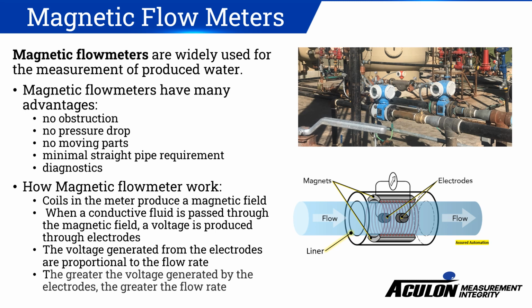How magnetic flow meters operate: when energized, coils on the meter body produce a magnetic field. When a conductive fluid is passed through the magnetic field, a voltage is produced through the electrodes. A non-conductive liner, typically PTFE or ETFE for produced water, isolates the meter body from the conductive fluid, preventing a short circuit. The voltage generated from the electrodes is proportional to the flow rate of the process going through the meter. The higher the velocity of the fluid, the greater the voltage generated by the electrodes, the greater the flow rate.